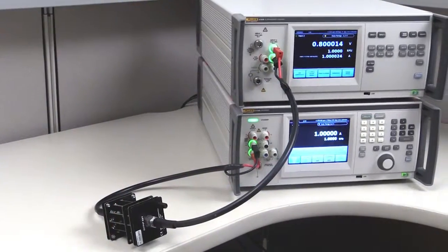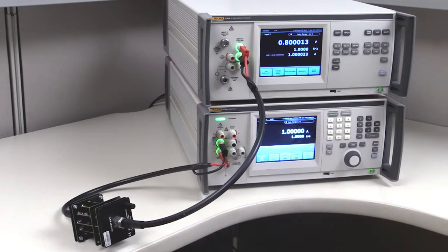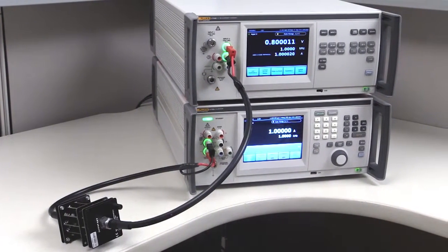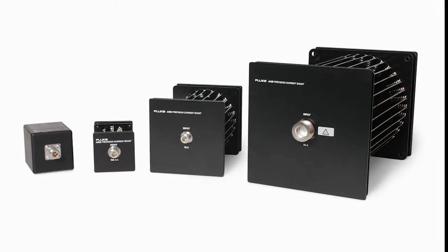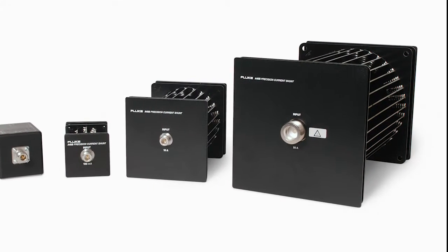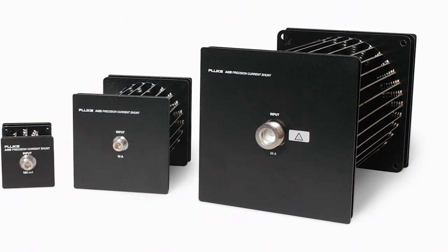The second major improvement is the 5790B's ability to make direct, absolute or relative current measurements with current shunts without needing to make any calculations. The 5790B is optimized for use with the Fluke A40B current shunts up to 100 amps to make absolute and relative measurements.